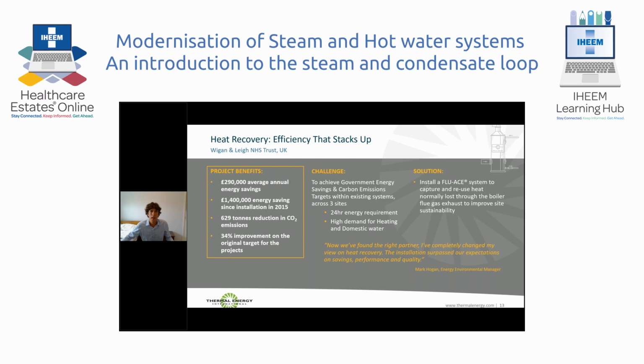This is a typical case study for a condensing heat recovery project installed at the Wigan and Leigh NHS Trust in the UK. Following the success of an earlier project, 3 additional projects were implemented across the trust. At Wigan Hospital, there is an extension to the heating loop of an existing FLU-ACE, including the critical care units, replacing the existing DHW shell and tube heat exchangers and plate heat exchangers. The Wrightington Hospital installed a FLU-ACE heating domestic hot water and heating calorifiers for building heating, and the Leigh Hospital installed a FLU-ACE from their 3 medium temperature hot water boilers, preheating the hydronic loop returns. That's the water coming back from the hot water circuit.